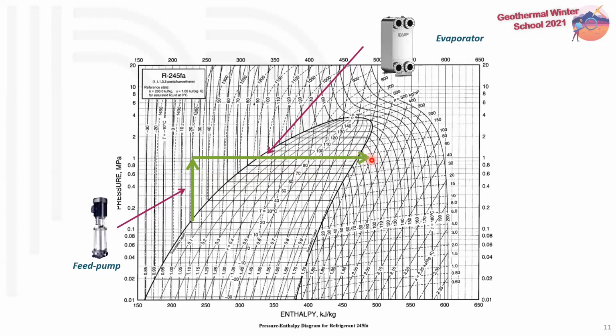Why do we go there? Because of the limitation of the expander. It's preferable to get a saturated vapor at the inlet of the expander in order to avoid having liquid in this part, because we can get some phenomenon really close to cavitation, and it will have a real impact on your equipment's lifetime.